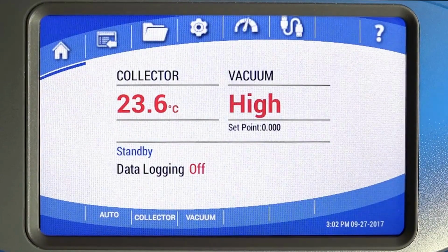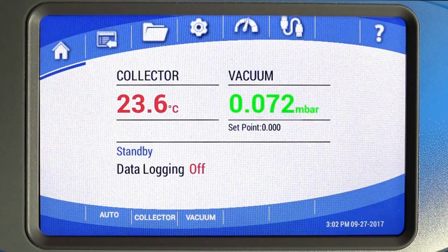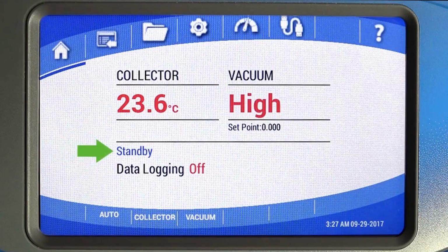Vacuum level is displayed on the right. When the vacuum level is above 5 millibar, it will say high. At 1.5 millibar or lower, it will change from red to green. Vacuum level can be displayed in millibar, Pascal, or torr. The current operational mode is displayed here as manual, standby, or defrost.